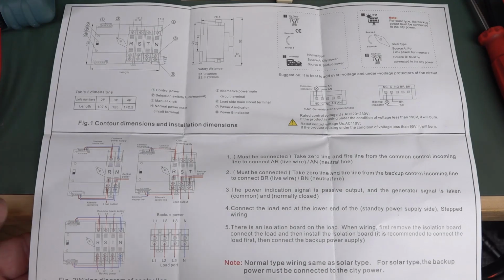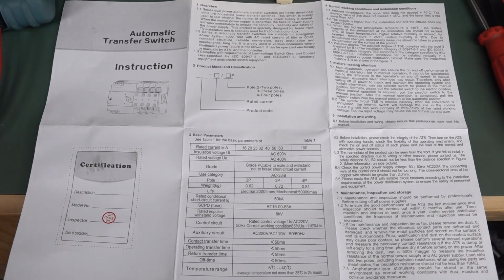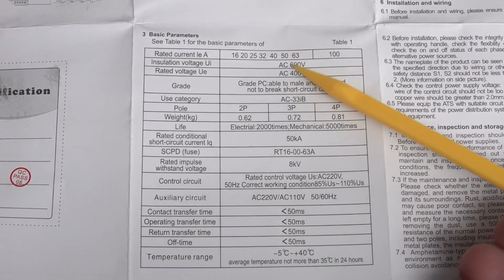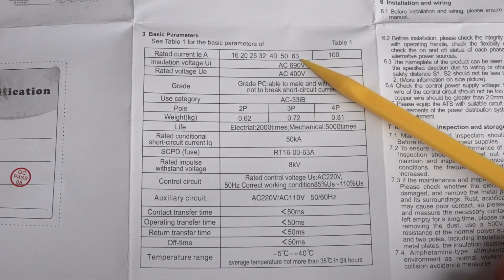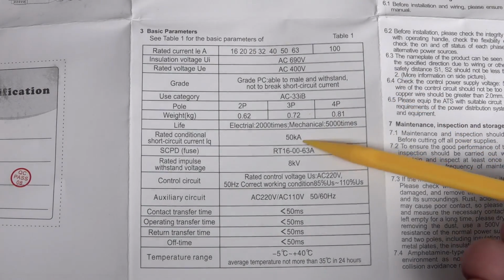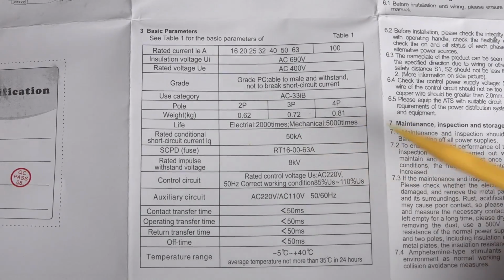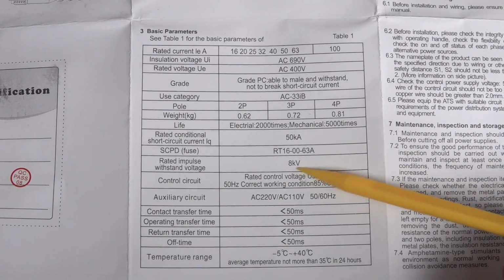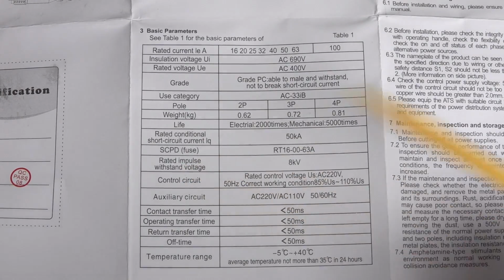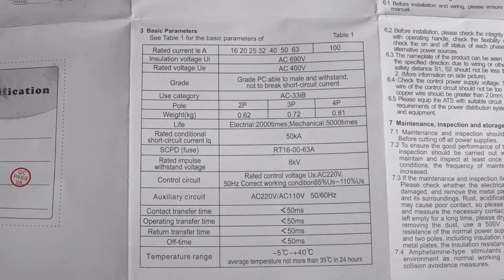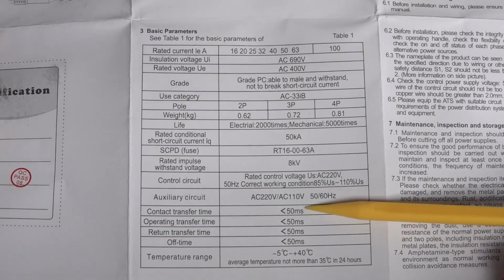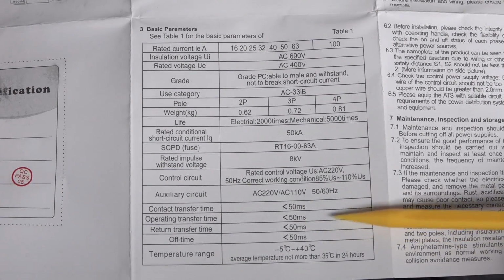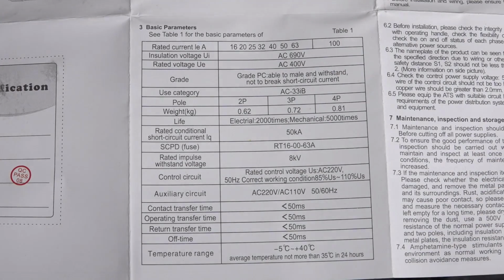For those that want to see it, there's the entire spec sheet there - what's on the other side I don't know, at least it's all in English. For those interested, it comes in different models; I've got the 63 amp one here. It looks like it's breaking current at 50,000 amps, kilo amps. It's rated for 8 kilovolt impulses, for the electronics and whatnot, so it doesn't arc over. Its transfer time is 50 milliseconds, so this is basically just a relay operation. You can get much more expensive electronic versions which have zero switchover.